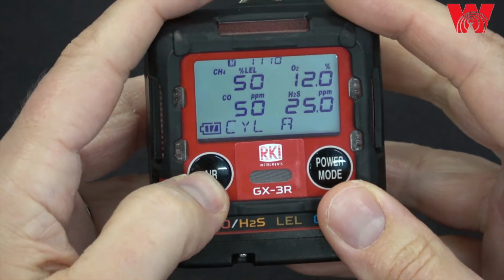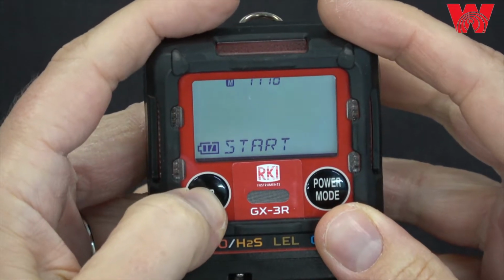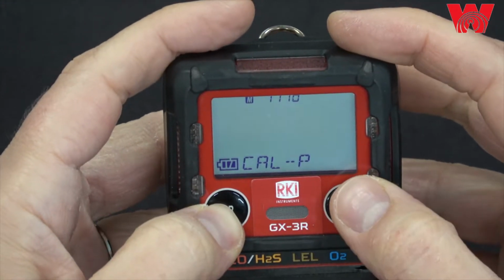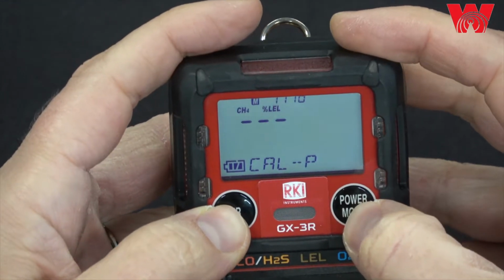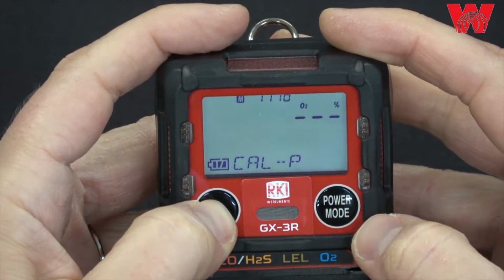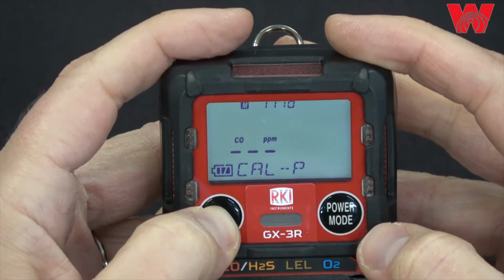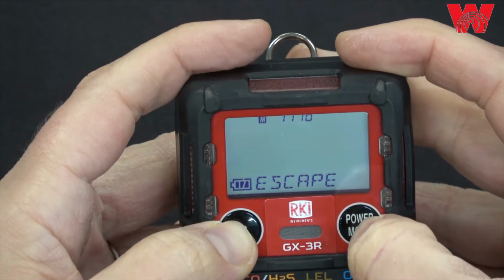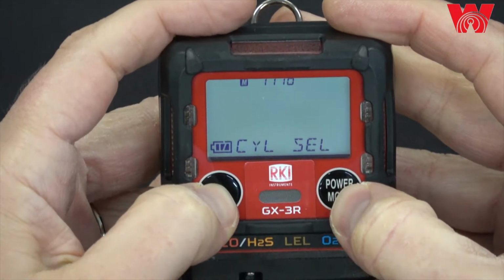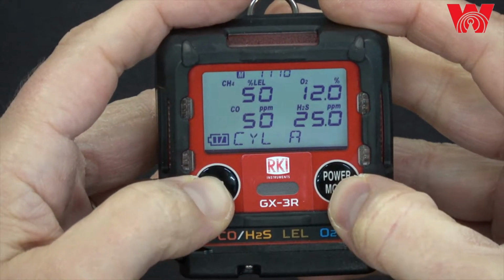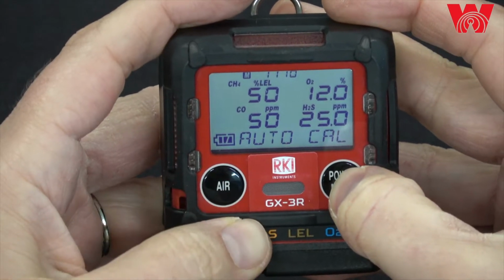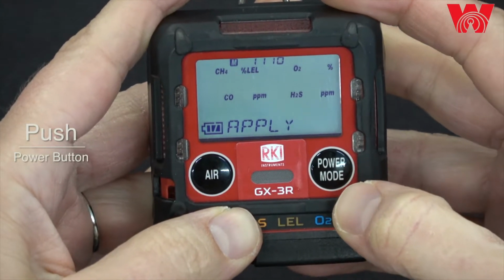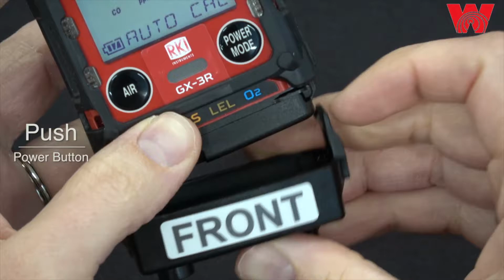If they don't match, use air to scroll to cal P, power mode, and here's where you can change the values for all of the different sensors. My values are fine, so we scroll to escape and back to this auto cal screen. I'm going to press power mode. The gas readings start to flash.